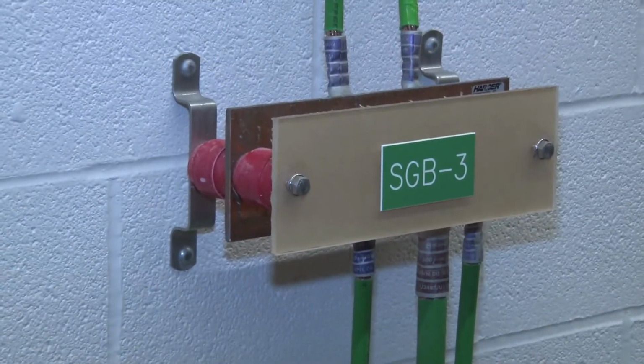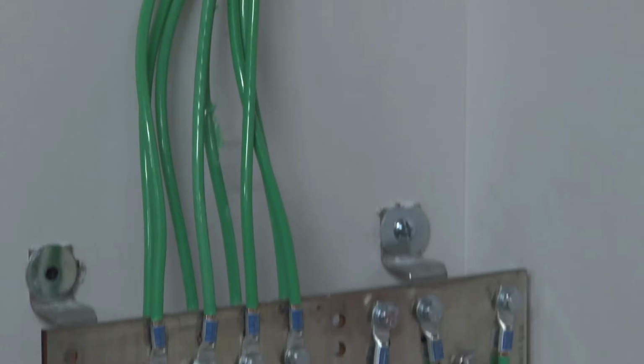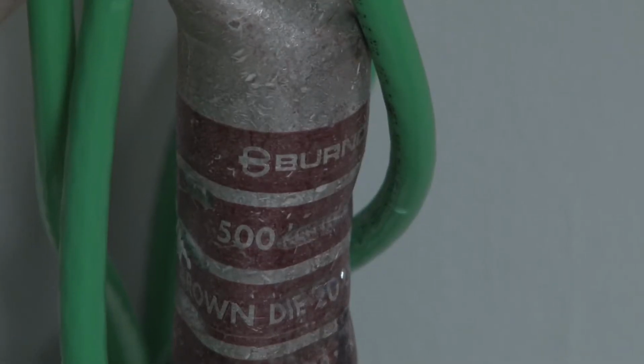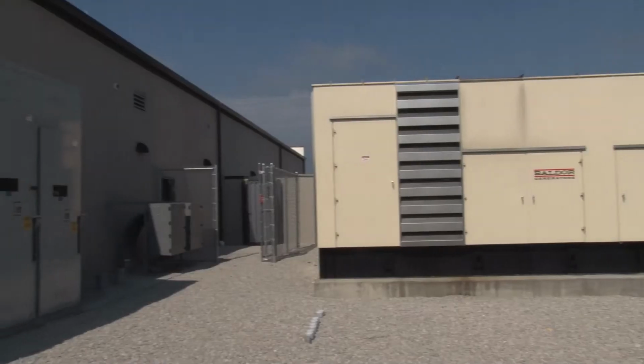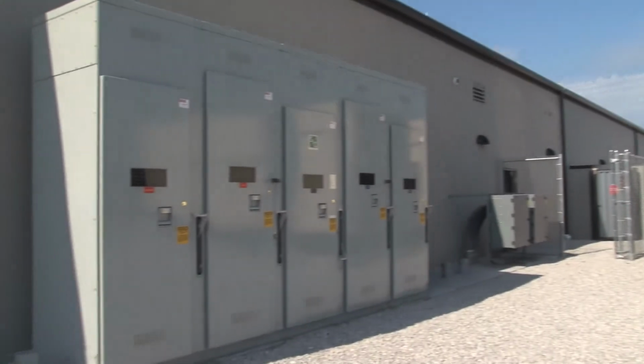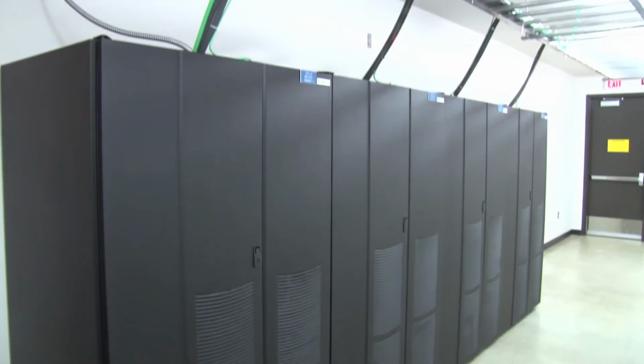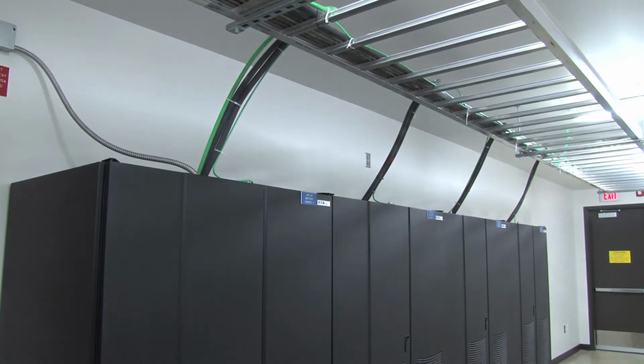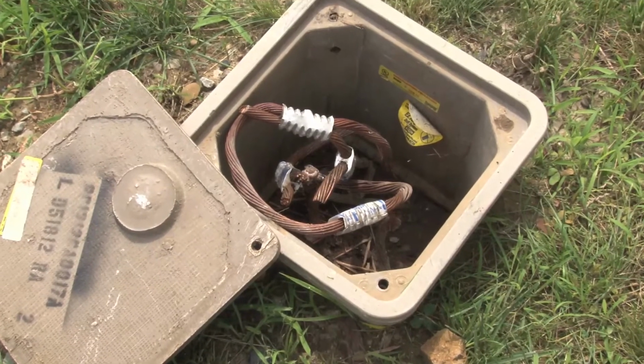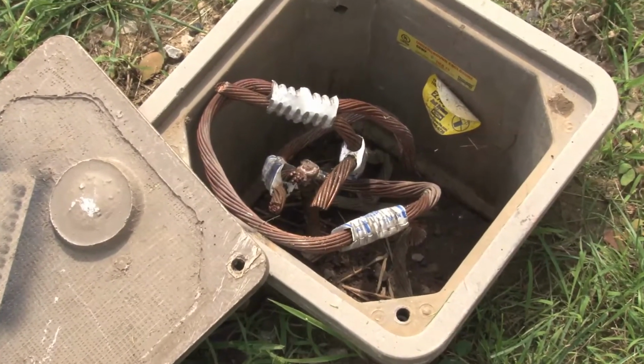A lot of times we're talking about the premier items, the power, the cooling, the infrastructure, security and such. Grounding always seems to be that lost item, but it's one of the most important, if not the most important component to ensure that power stability and delivery. For proper grounding, you need to use the right conductor, and that should be copper because of its reliability factor. Whether it's our switch yard with a web of grounds underneath, or it's our data center equipment or our data center loads, the actual server equipment, all of those have to eventually come back to a ground that makes good connection with Mother Earth. And so we can use a variety of rings to do that.